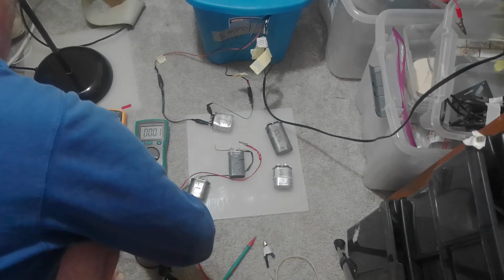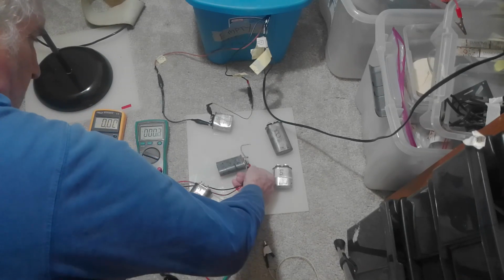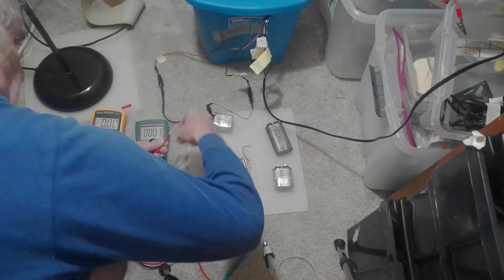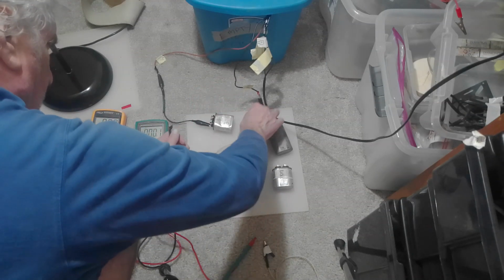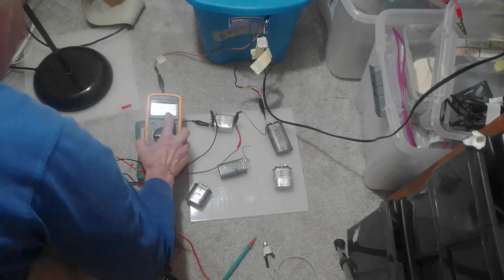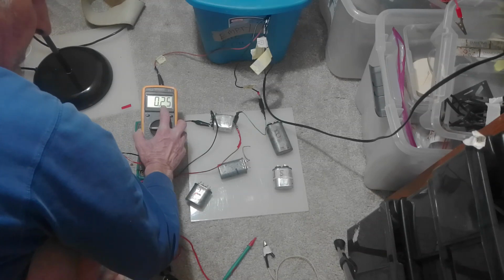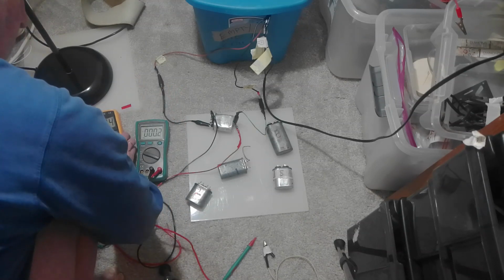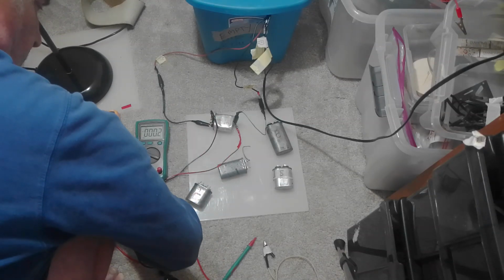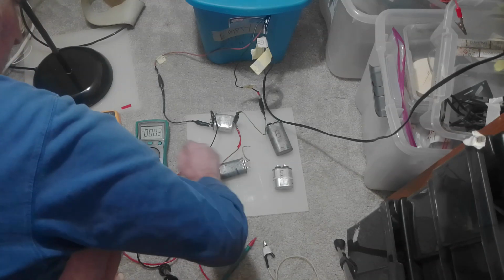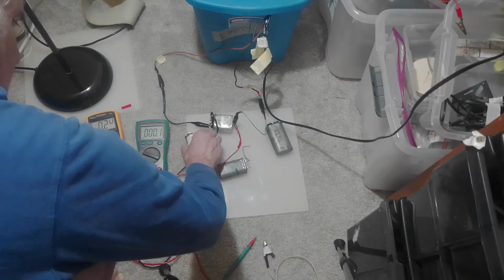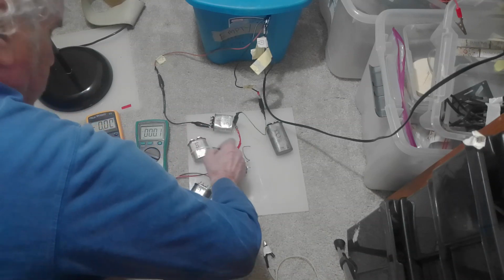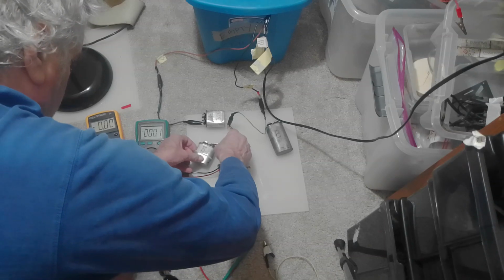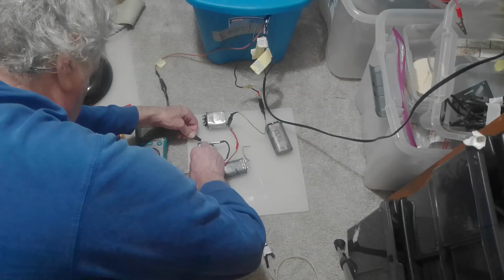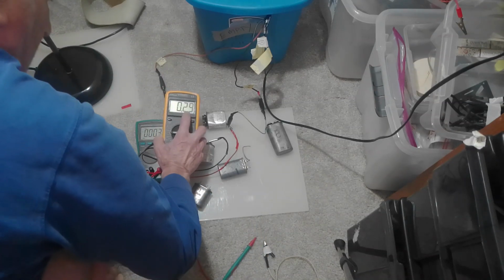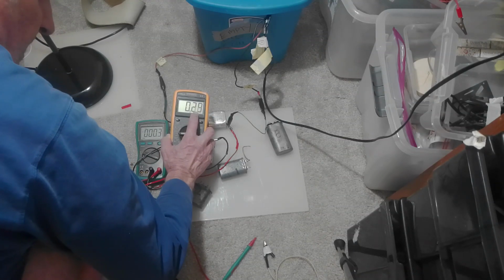Okay. Now measuring current. This is circulating current. There's no load except for the cap. Current is 250 milliamps going to this 4 µF run cap. So let's try a 5 µF run cap.